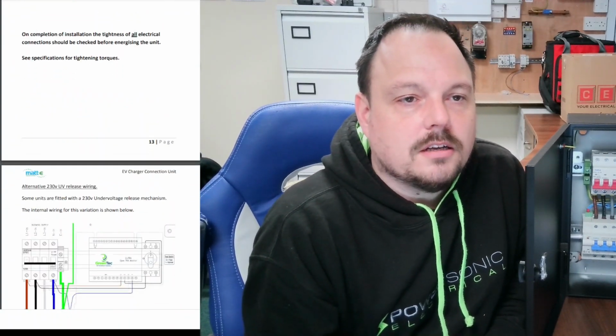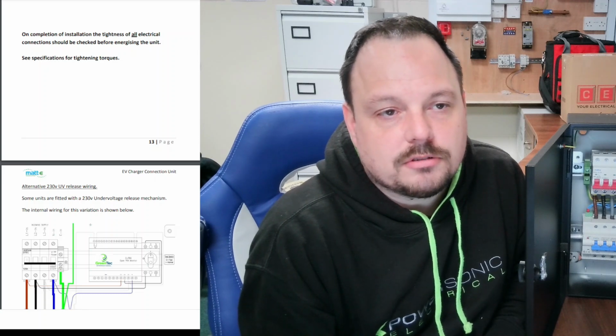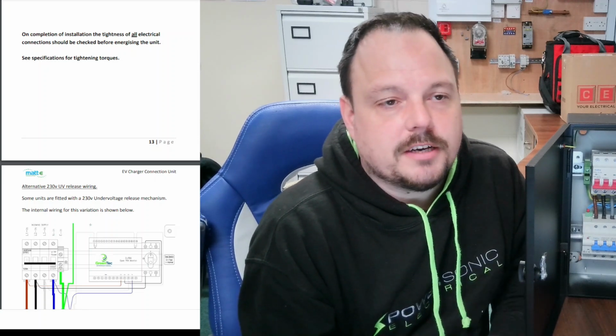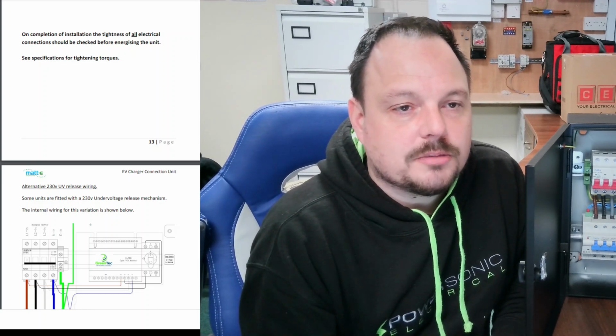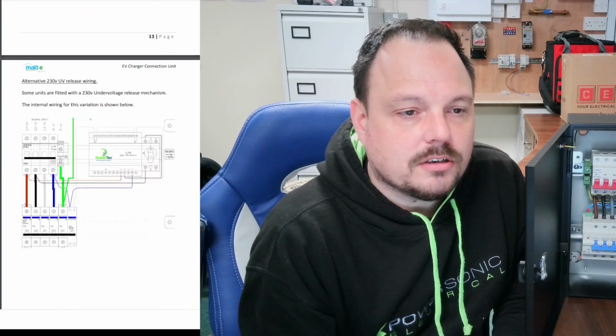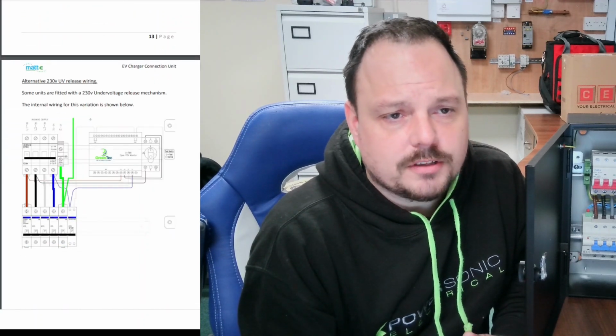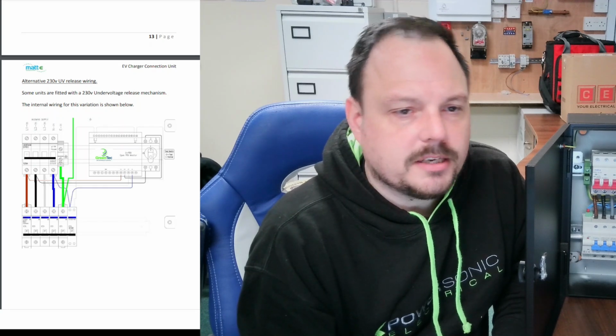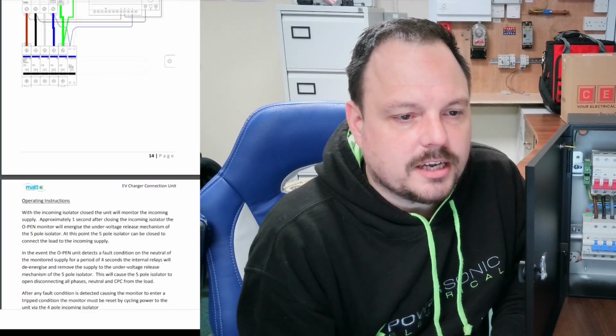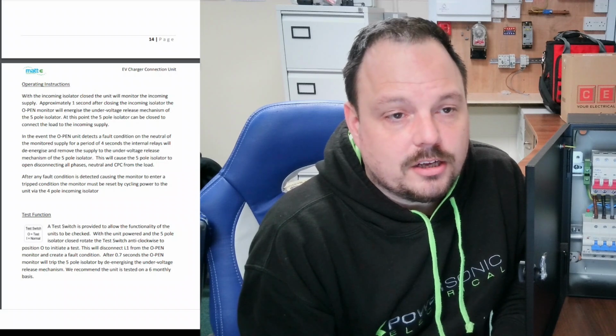It says here, on completion of the installation, tightness of all electrical connections should be checked. So even the manufacturer ones, check them all. And there are specifications for tightening of the torque values. Some units have the 230 volt under voltage release mechanism. This one doesn't, and there's a diagram there for that one. There's then the operating instructions.